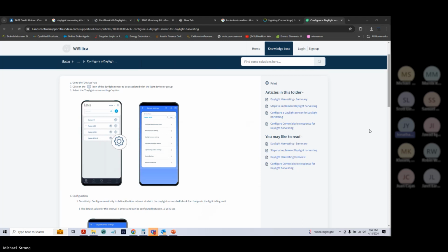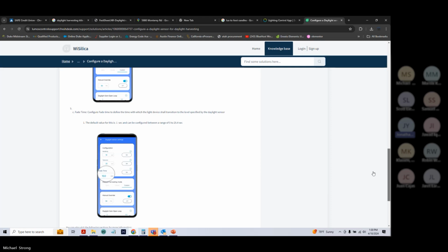So when no one is in the room, the lights will still stay off, even though there is daylight sensing. Only when someone enters the room or the area will the lights turn on, and then the daylight sensor will either dim the lights or increase the light intensity. We have a couple of other settings for daylight sensors, such as the interval, the amount of time between the measurements, when the lux levels are taken, so that your light levels aren't changing so much. You can set it for 10 seconds, 10 minutes, an hour, however you want it. And we also have a fade time setting, so if you want a slower fade time, you'll be able to set that.